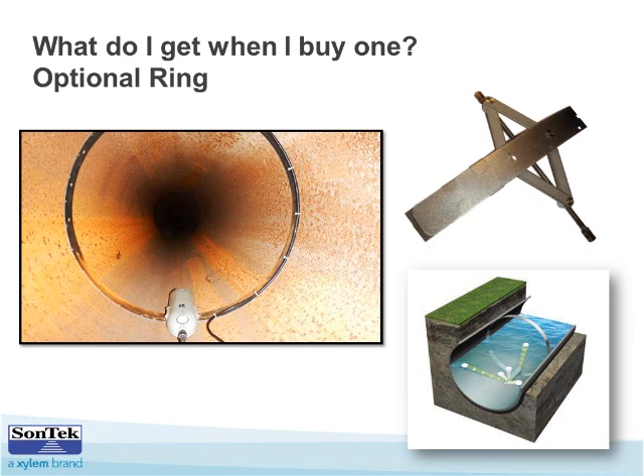If you get that in there and you realize, gee, that pipe's full all the time, you can crawl in there after the fact and just invert the thing 180 degrees and mount that instrument up at the top, or even at a 45-degree angle, and just modify it through the software. Just tell it where its X and Y coordinates are now, and it's that simple to change the locations of it pretty quickly.